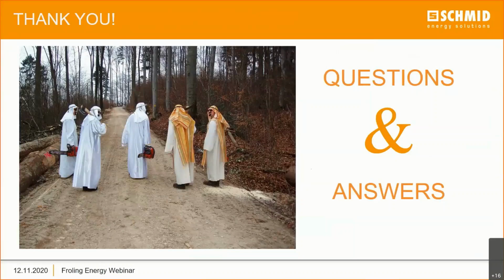So it's good. Another one of our experiences, Marcel, has been the frequency of cleaning. Some of the earlier boilers and pellet boilers that are being used in commercial situations, we find that one of the policies was every 600 hours of runtime they need to be opened up and cleaned, brushed out, even though they have various cleaning mechanisms. What have you discovered in that, Marcel? What would you say the cleaning time is?